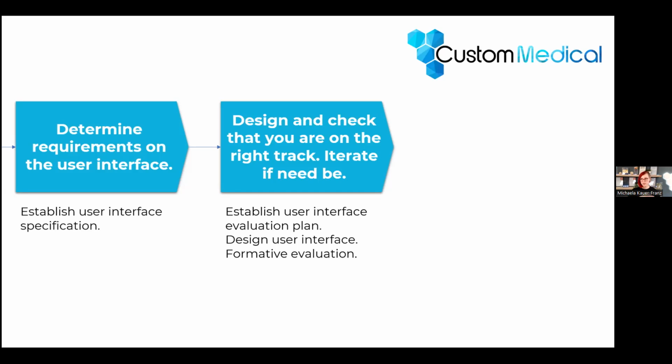Formative testing, just to make it very clear, is not required. It's not a mandatory step in the process unless you have decided to integrate formative testing into your own usability SOPs, so your standard procedures internally. If you've written down that we are doing formative testing, for sure your notified body will have a look at your formative testing. If you haven't included it, but you're just saying we're doing the design and then we are going to do the summative evaluation, everything's fine. Nobody's going to ask for it.